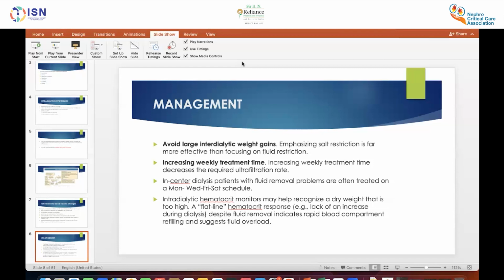But the problem is, sir, tell me, do we check at the start of dialysis and end of dialysis, or can we monitor it? No, after 2 hours of continuous dialysis, it is a continuous monitor. It is a sensor attached, and there is a monitor with a graph, like your multi-para monitor. That small monitor will be fitted above the dialysis machine, and continuous, real-time monitoring will be done.